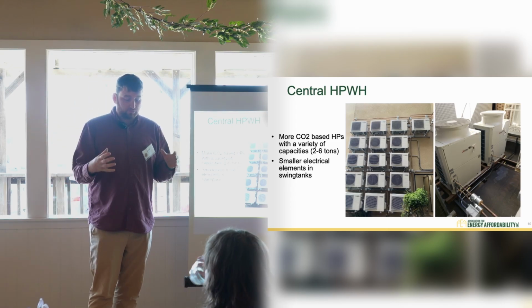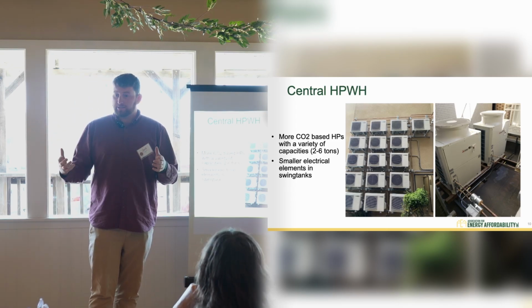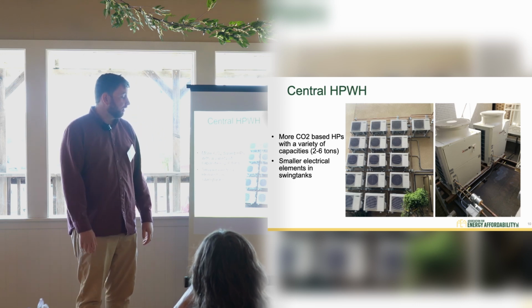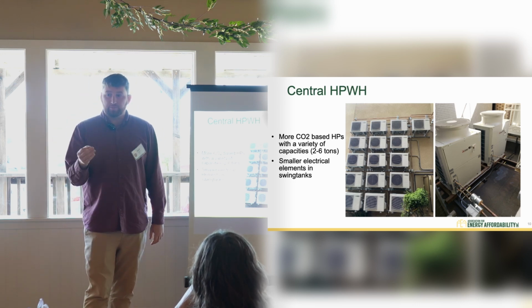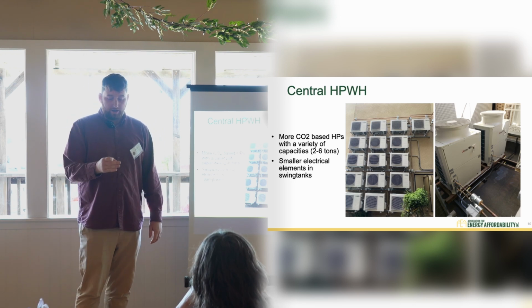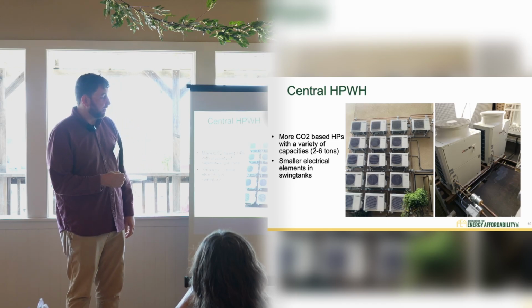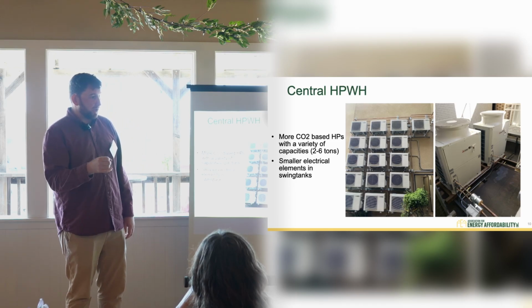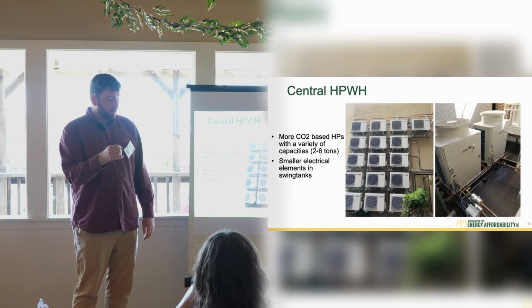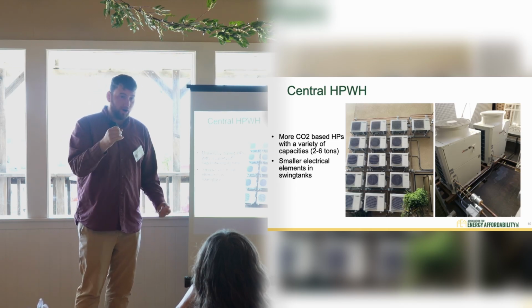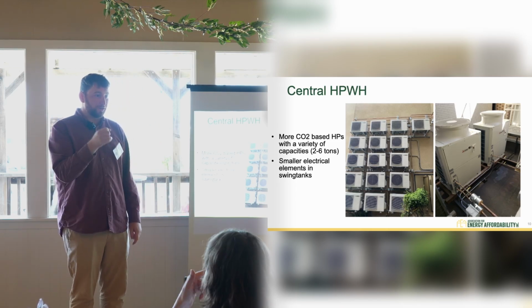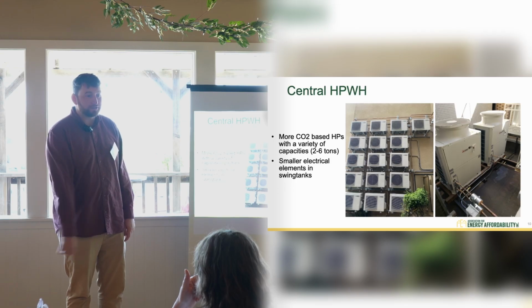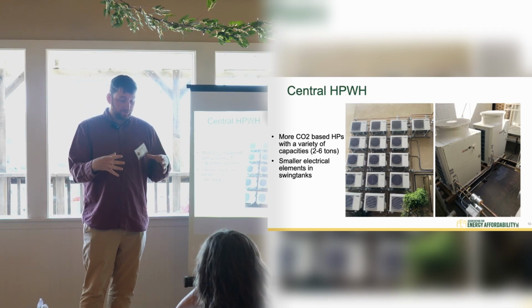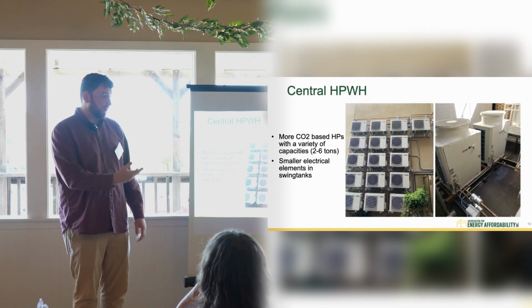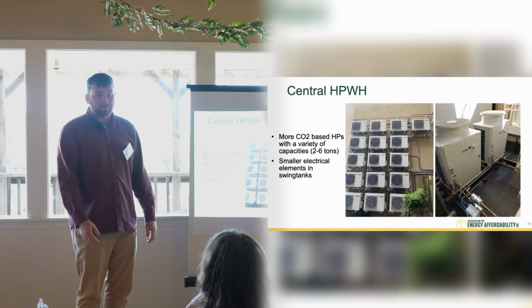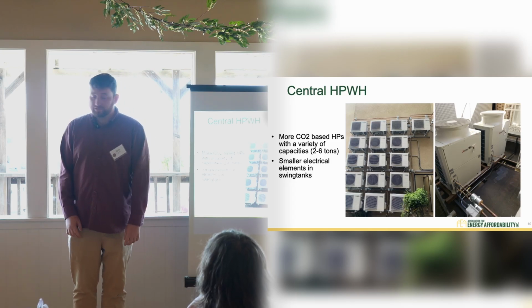Also, you have these residential electric resistance tank type water heaters that you can use for swing tanks, but the ports on them are tiny, 3/4 inch. We finished a project where the swing tank has a 3/4 inch port, and it's for a 101 unit building. All of the flow of 101 units has to go through a 3/4 inch port. And so smaller elements, larger ports, and we'll see more projects get done. Next slide, please.